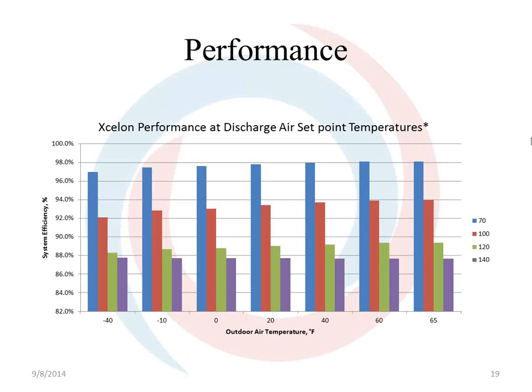Alright, these are some more data gathered on some different set points. And you can see at 70 degrees discharge temperature, which is common for most makeup air units, 100% makeup air units, you can see at different outdoor air temperatures it maintains a 97-98% efficiency. At 100 degree discharge temperature, it's still above 90%. It's 92 to 94. At a 120, it goes a little bit below the 90% range.